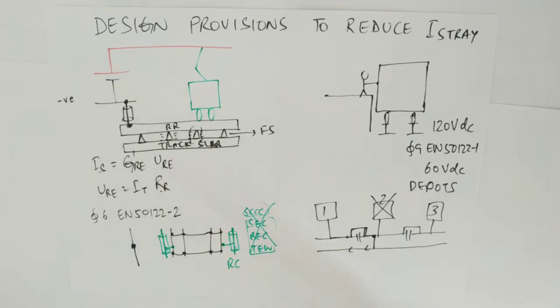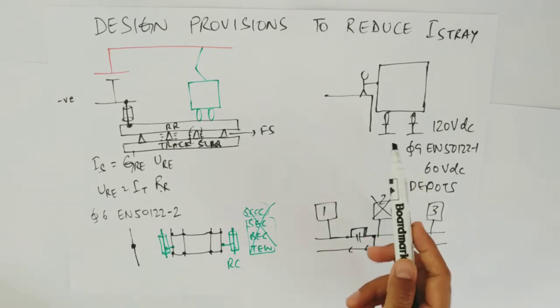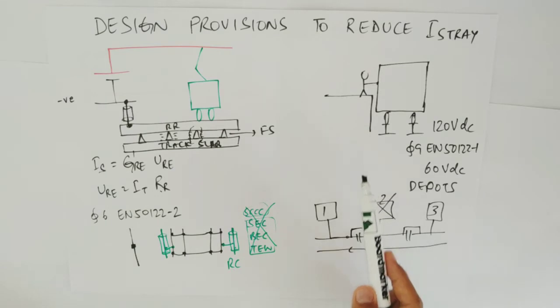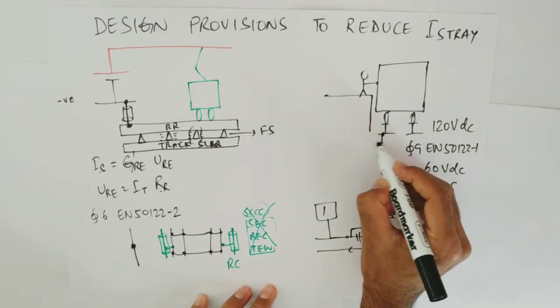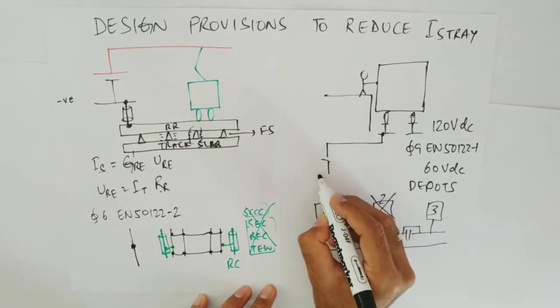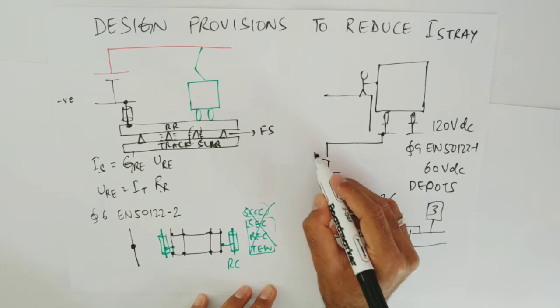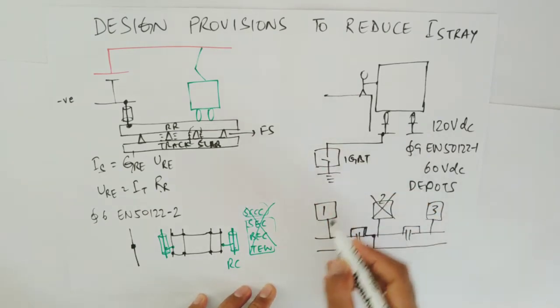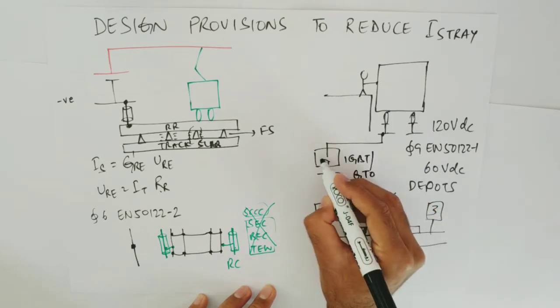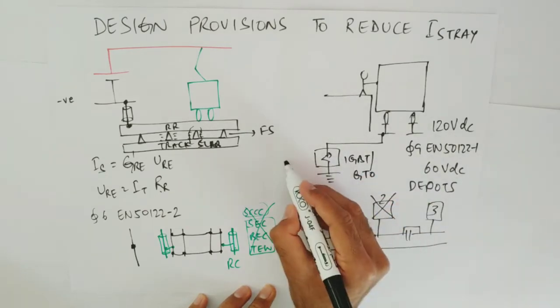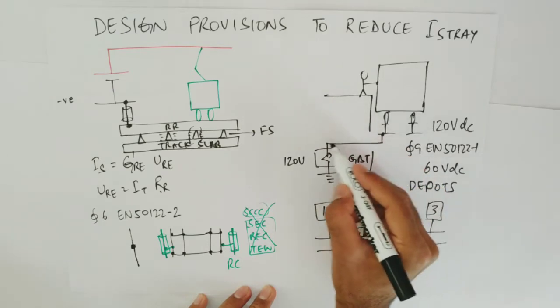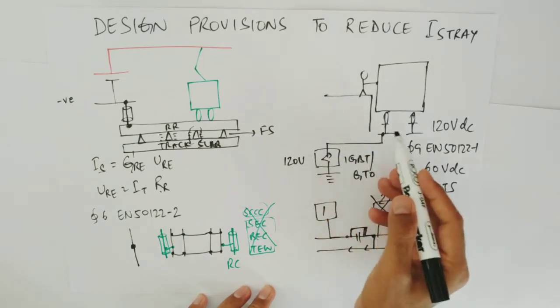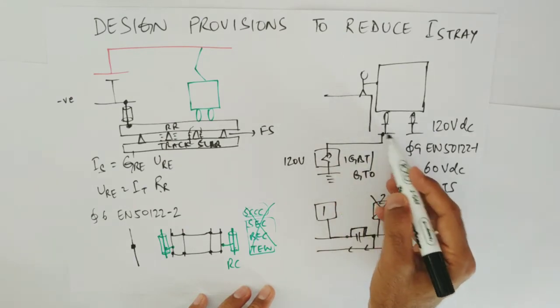To avoid this, we provide an extra device connected to the running rails — a voltage limiting device (VLD). This device acts as an intelligent switch using an IGBT or GTO. It triggers and connects the running rails to earth when the voltage goes above the set value (e.g., 120 volts). Once the running rail voltage decreases, the switch opens and the complete system returns to floating.